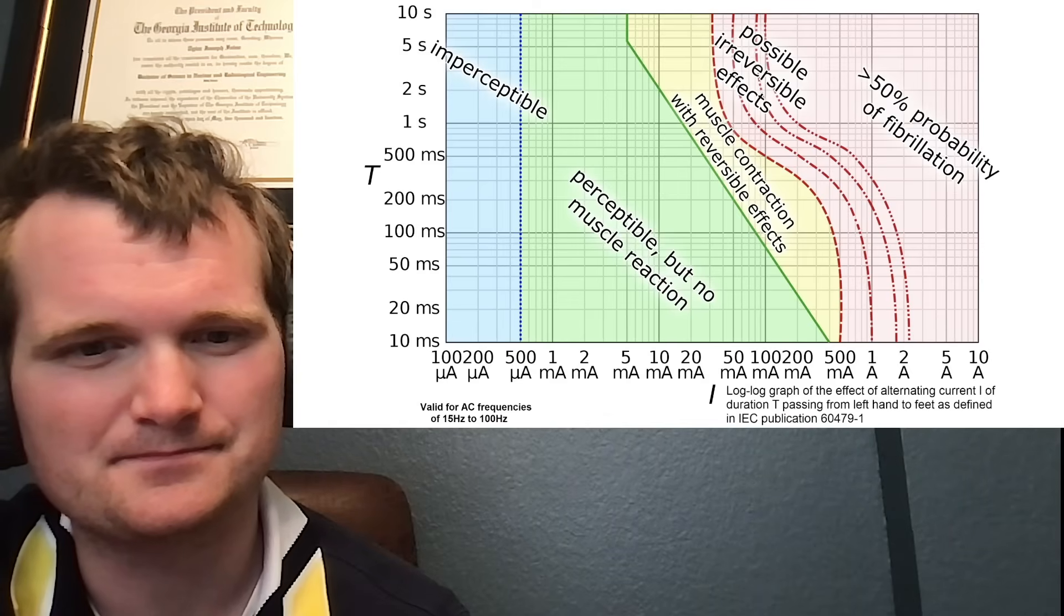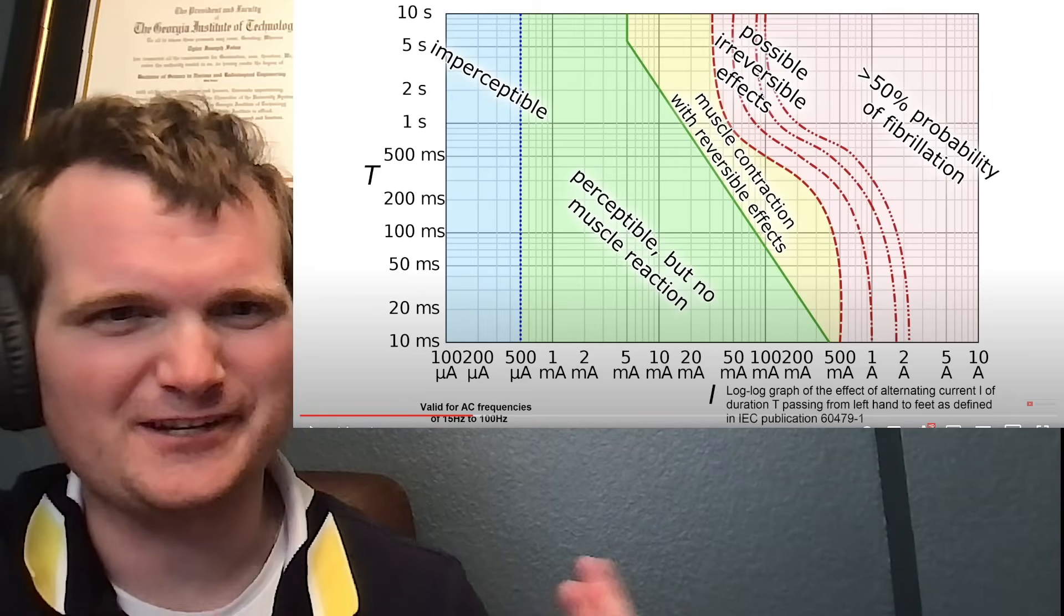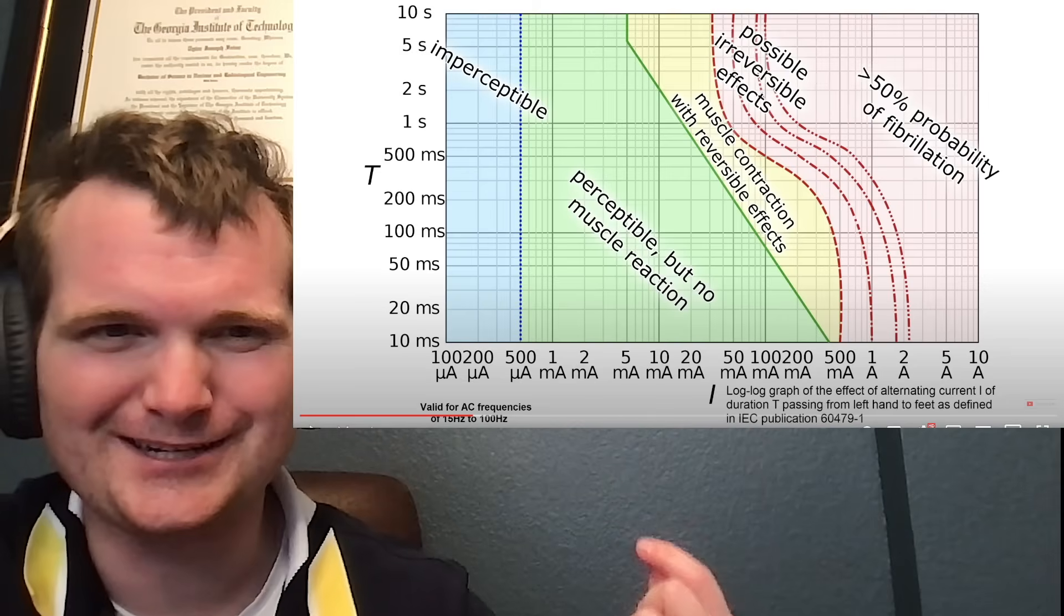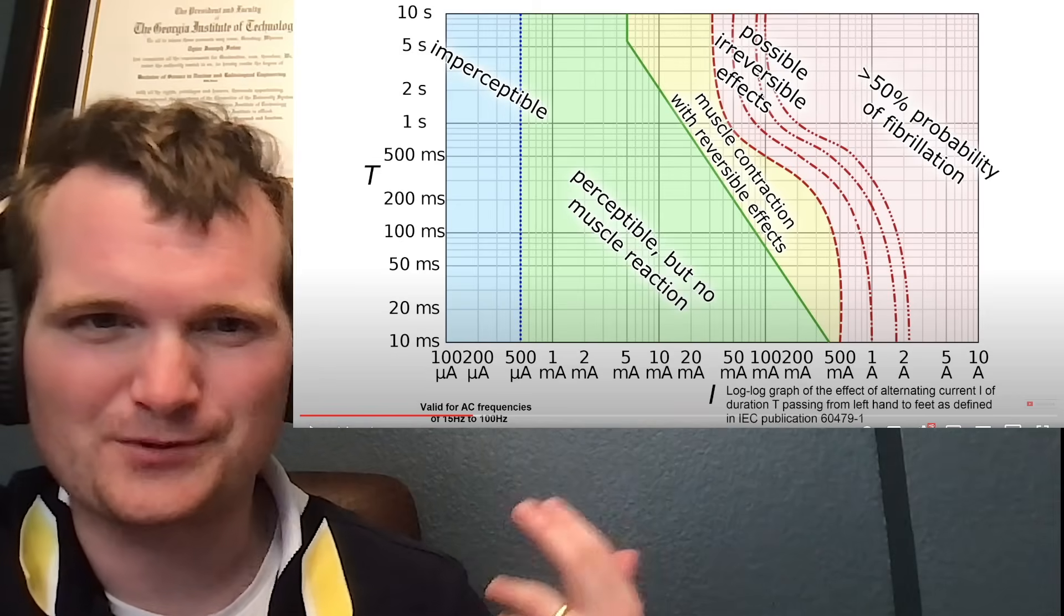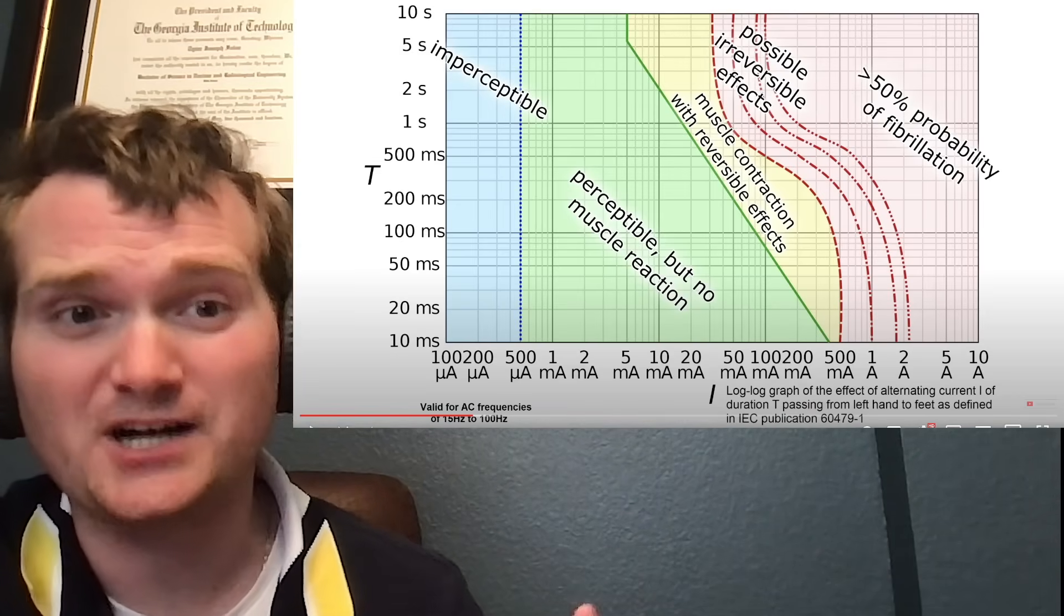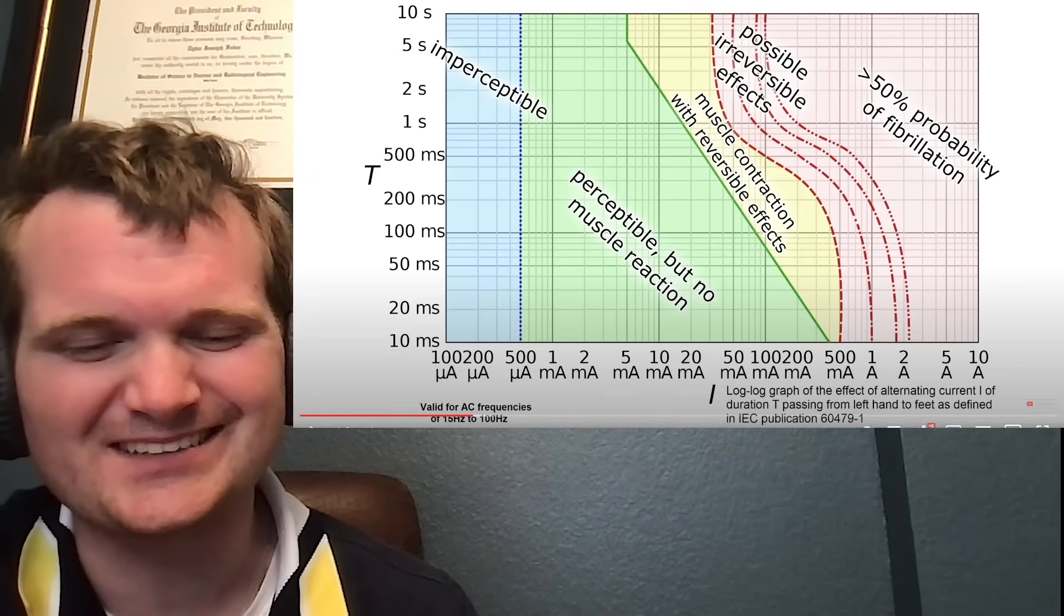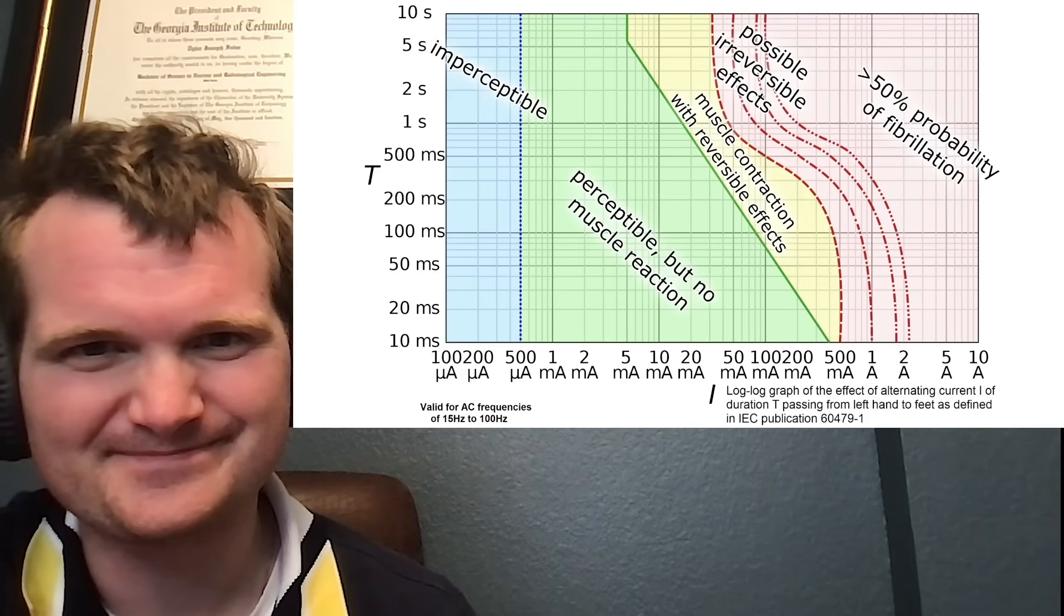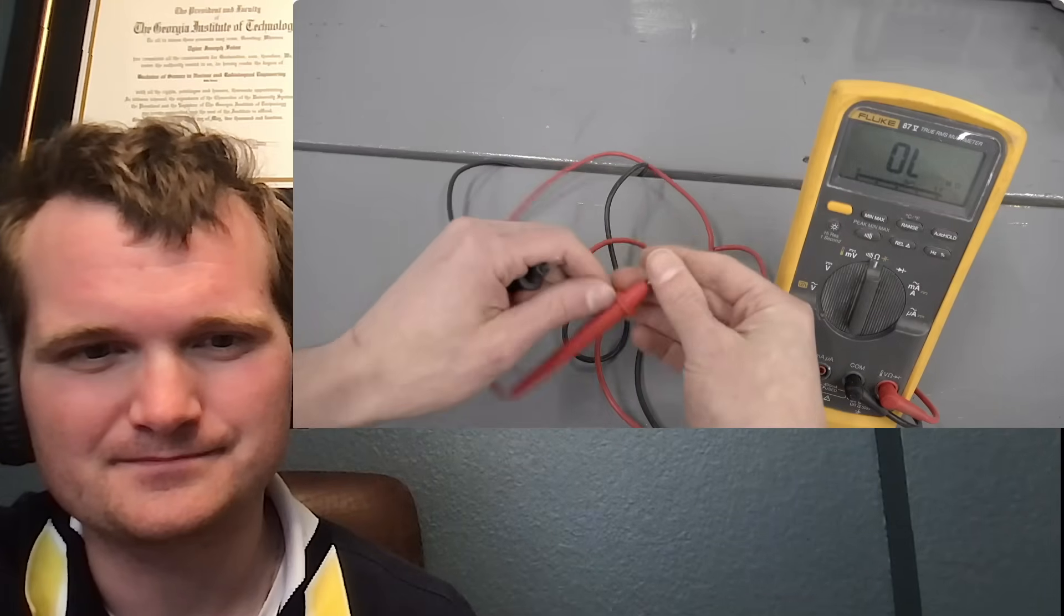Let's take a look at this electrical shock hazard chart. Okay, yeah. Anyone who's had some electrical safety procedure, there's something like this that's always like an addendum in your little electrical safety handbook that looks at voltage, current, what type of personal protective equipment you need for the job, for your shock hazard, and also your arc flash hazard. And there's usually something like this in the back of all those procedures. Nothing about voltage on here at all, only current. What gives? This assumes that that source can put that current through you. Yeah. Which means it has to have a sufficiently high voltage to do so, as well as a low enough impedance.